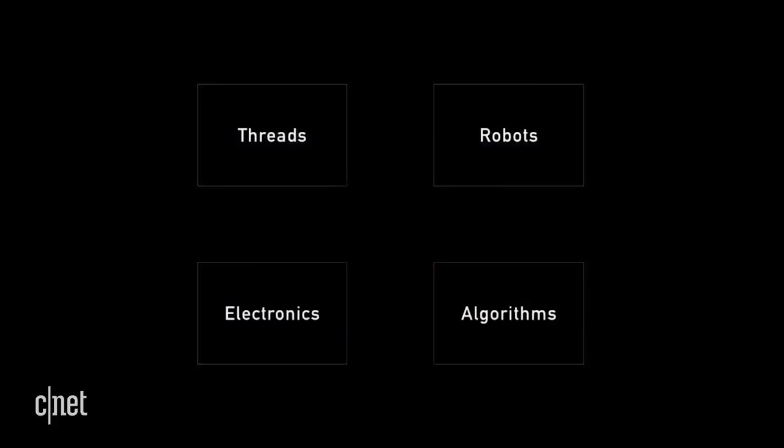You really need this to be done with a robot, because it's very tiny and it needs to be very precise. So you don't want to pierce a blood vessel. So for each thread, the robot looks basically through a microscope and inserts each electrode specifically, bypassing any vasculature, any kind of blood vessel, and making sure that it can be inserted without causing trauma or with minimal trauma.